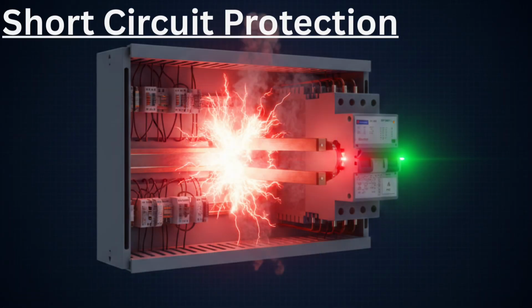Short circuit is one of the most severe electrical faults. It occurs when phase-to-phase or phase-to-neutral contact happens. Current increases instantly to extremely high value. This can cause heavy arc flash, mechanical stress, busbar damage, breaker explosion. To prevent this, air circuit breakers are equipped with instantaneous magnetic trip. This type of protection works in milliseconds. The faster the fault is cleared, the less the damage. Short circuit protection is critical for crew safety and system reliability. Regular inspection of breaker mechanisms ensures proper functioning during emergency.